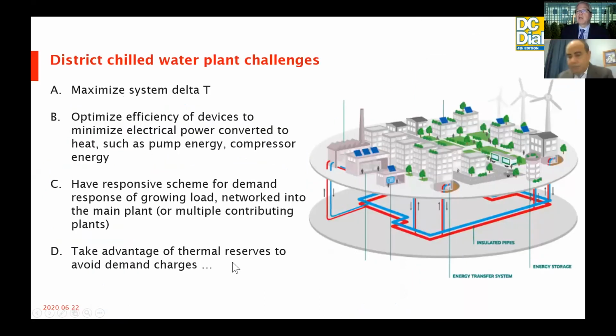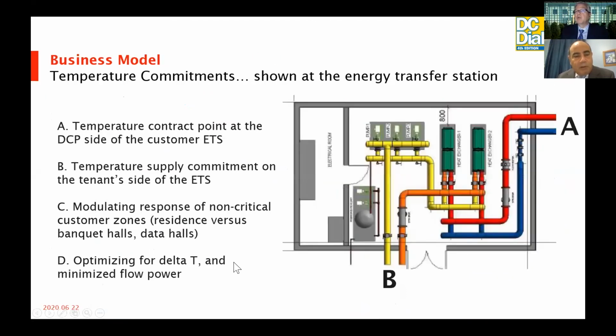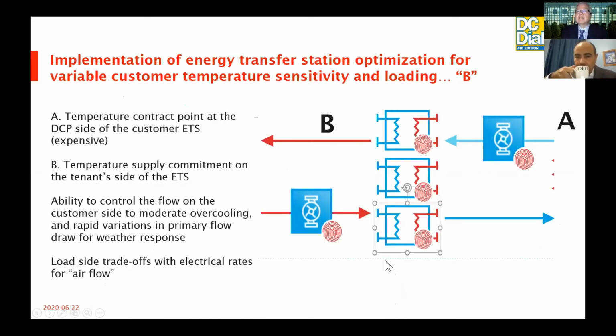So the new technology also extends to district cooling plants, whether you're running with a temperature contract to supply temperature to the building, or if you're on the building side and you have a temperature and load contract, we can create digital models, and they exist today, to optimize both scenarios. And you're able to pinpoint within the building if there's an air side complication.